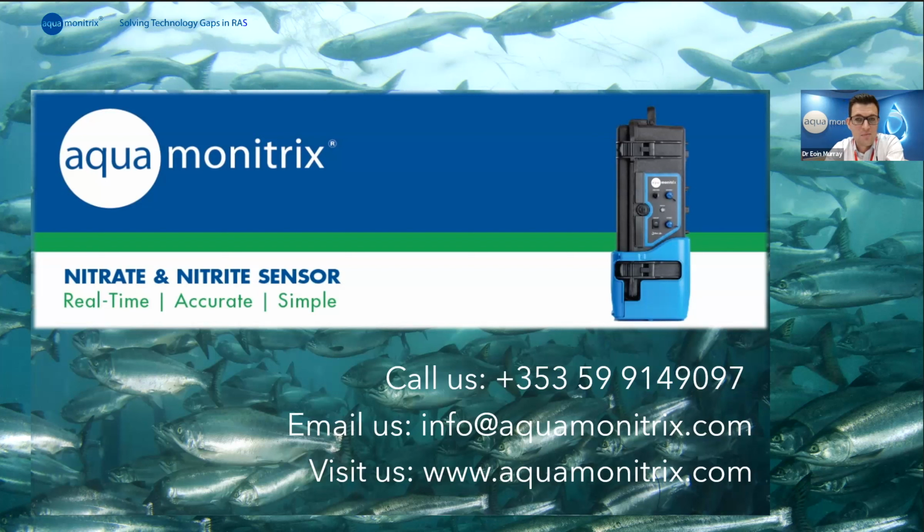In terms of accuracy and performance, we really stand over it. For most applications, we expect 95% accuracy and precision of plus or minus 5%. And that's across salinity, across freshwater and fully saline. So in terms of analytical performance, we really expect lab quality analytical performance from the online analyzer. Just to make a point of that.